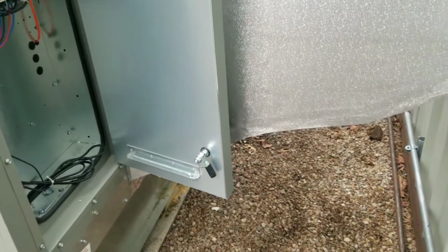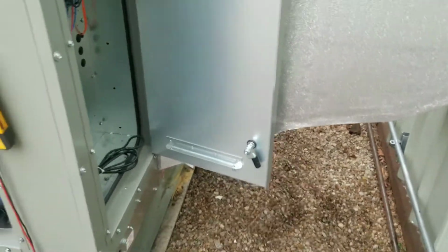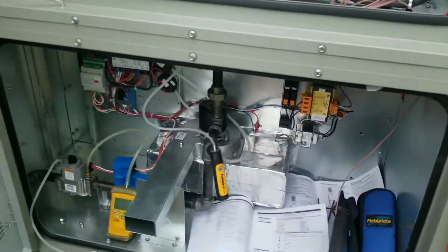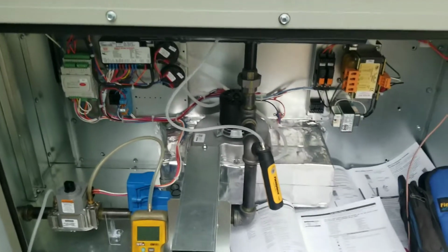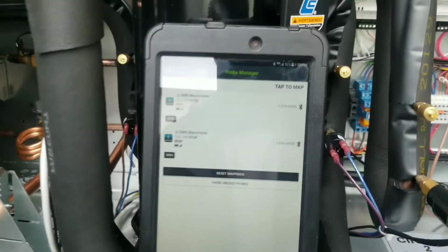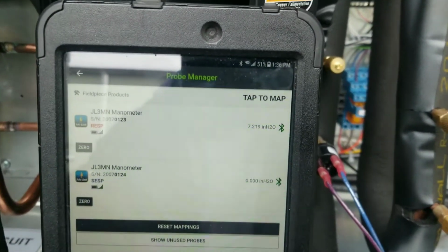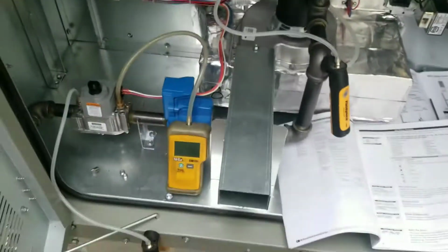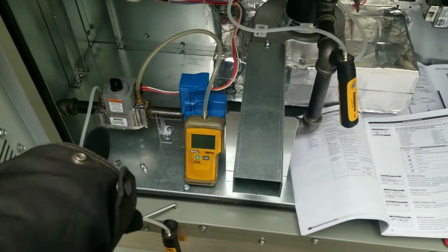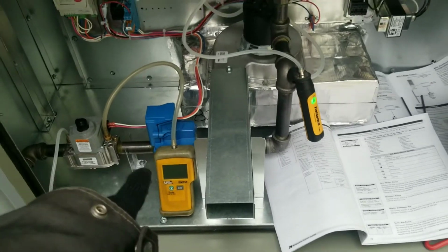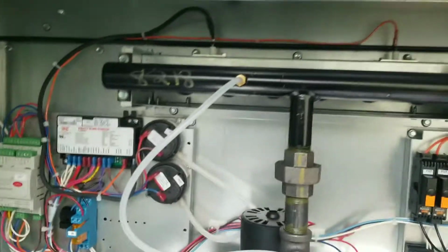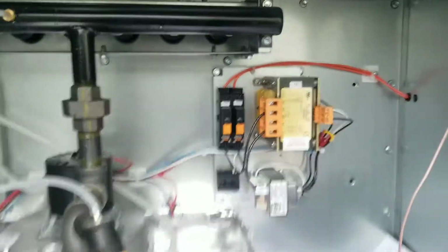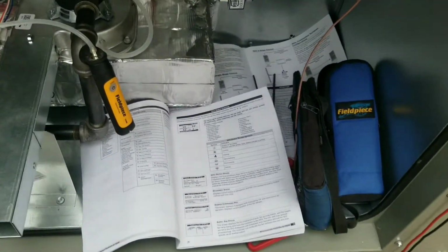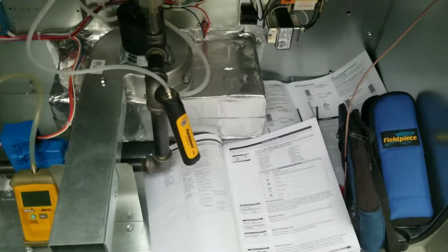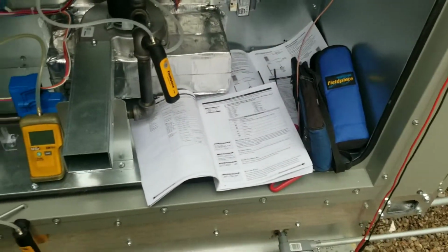letting this heat exchanger burn off. So everything's going to go into the building. That'll be interesting. So once they get that in test, we should be good everywhere else. I'm running about 7 inches water column in, and we'll check outlet of the gas valves, 3.5, and then we got a modulating valve for the burners. Not a bad little setup for Greenheck. The control's nice. I went through some of the literature here, and we'll have to do a full startup on the cooling, but for now they'll have some heat.